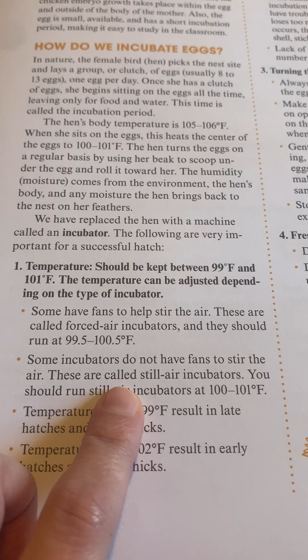Some incubators do not have fans to stir or mix the air, and those are called still air incubators. Still air incubators, if the air is not being mixed or stirred, get run a little bit warmer, 100 to 101 degrees Fahrenheit.